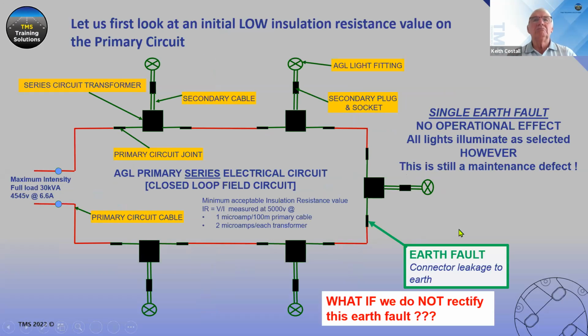So what are fault conditions? Well, our cables live in the ground, in ducts or directly buried. So we have an earth fault potential because we have to connect these transformers to the distribution network, the primary circuit. And these connectors are designed to be watertight, but over time deteriorate. And this is the potential where we can get leaks, earth leakage. So we do have earth leakage. We have an allowable earth leakage in the system by the nature of where it lives. But it is a fault. Now, just remember, one earth in a field circuit has no operational effect on the illumination of the lights, because this is a closed loop circuit in normal operation. And therefore, one earth has no operational effect on the illumination of the lights. It's only when a second earth comes. Therefore, what could happen?